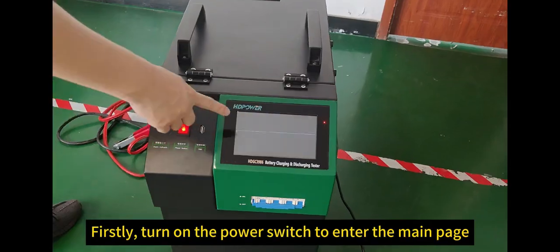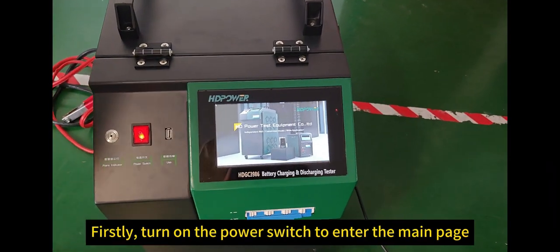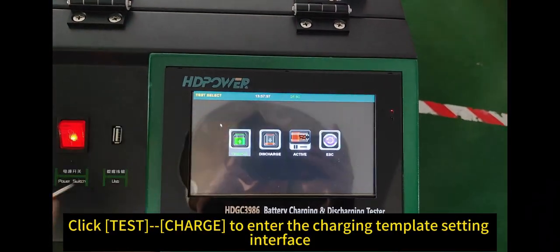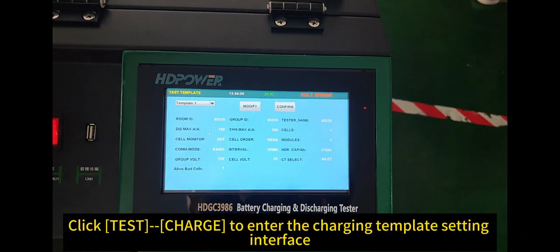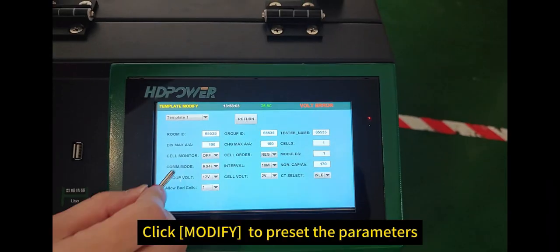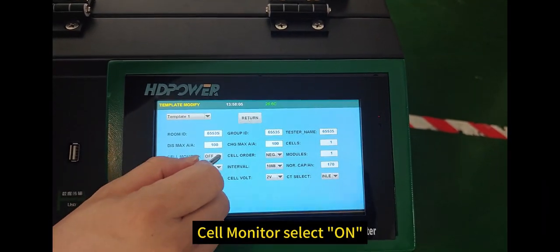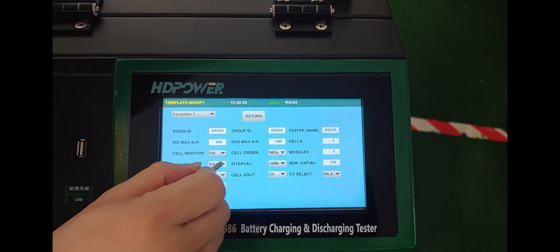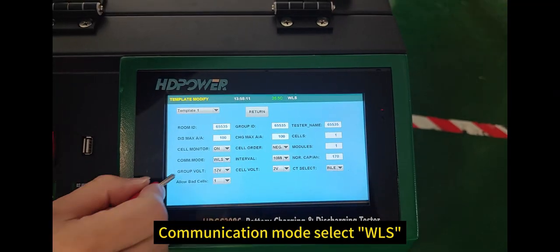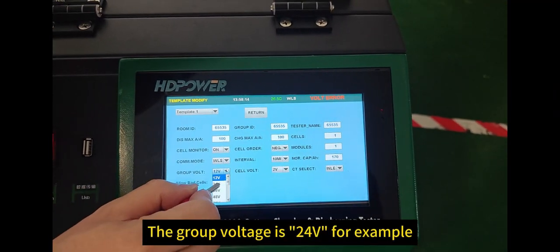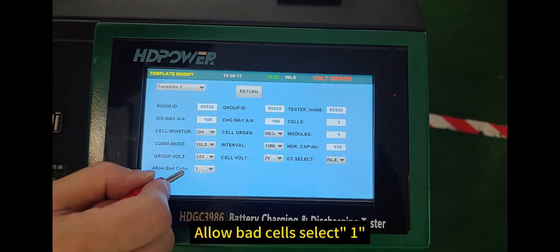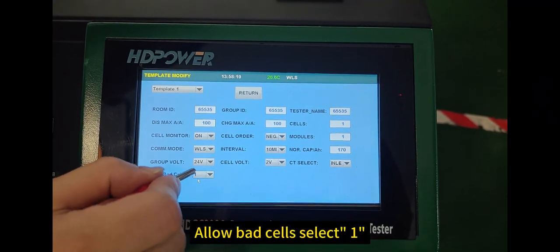Parameter settings. Firstly, turn on the power switch to enter the main page. Click Test Charge to enter the charging template setting interface. Click Modify to preset the parameters. Cell monitor select on. Communication mode select WLS. The group voltage is 24 volts for example. Allow bad cells select 1.